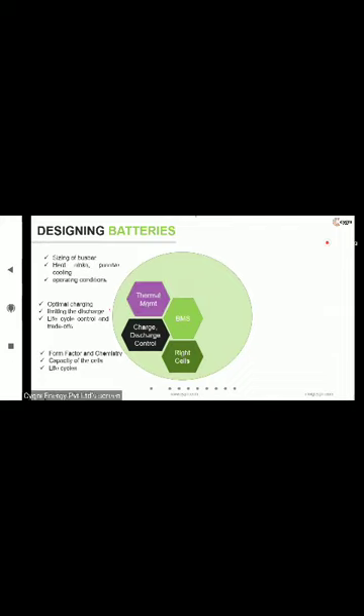The next thing is thermal management. You need to provide heat dissipating elements like heat sinks. Bus bar sizing is also quite important because the bus bar carries all your current. When you have higher current passing through, the bus bars need a higher area of cross section so they can dissipate the heat.